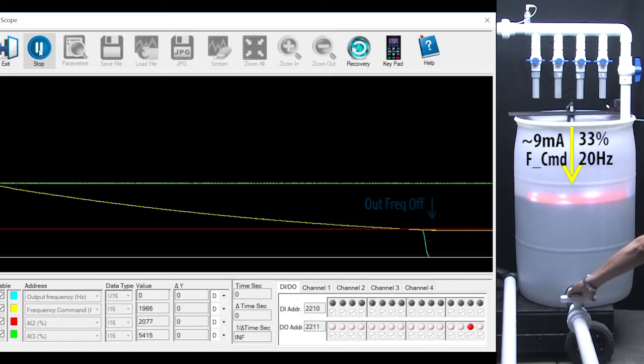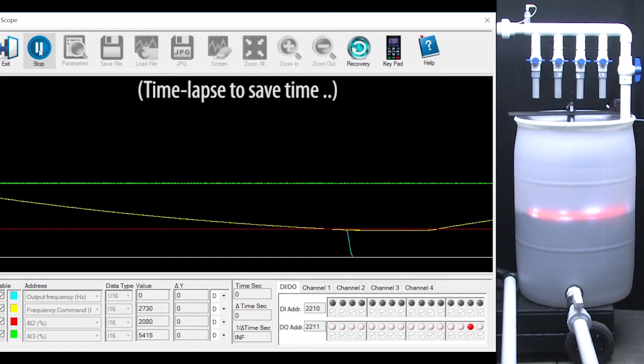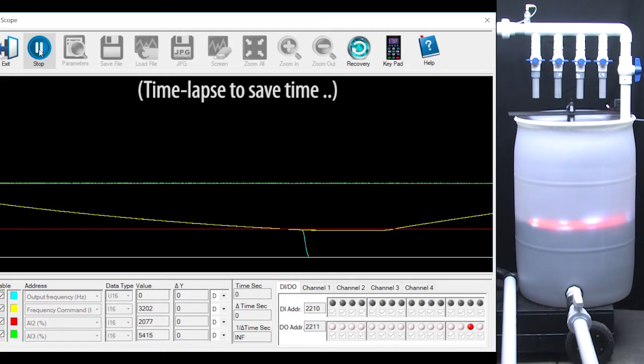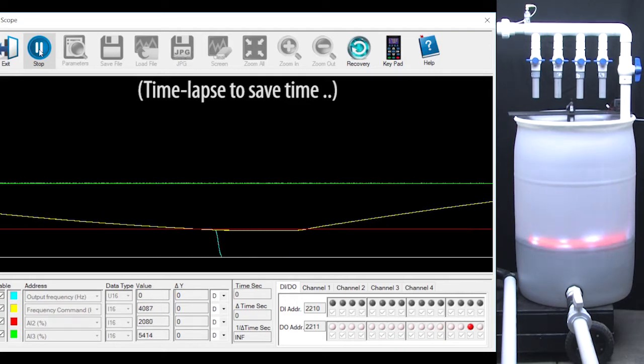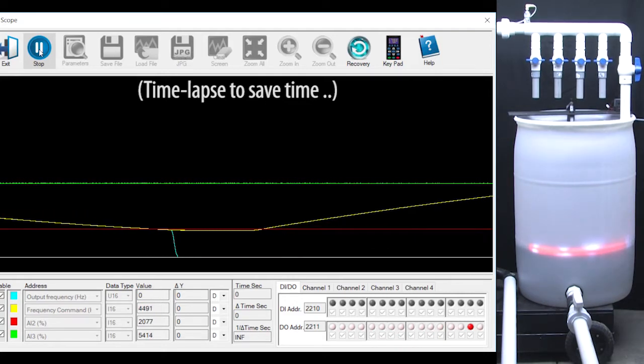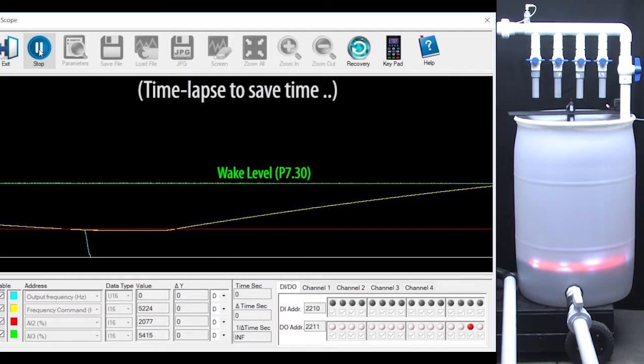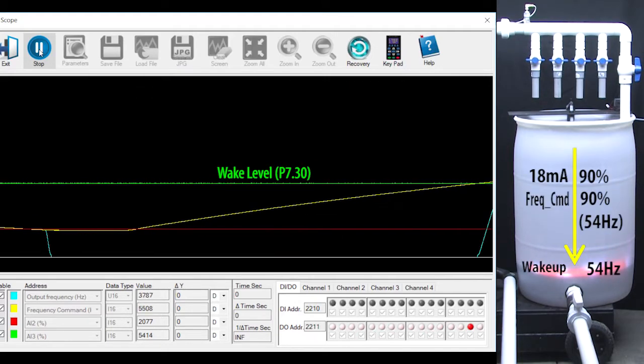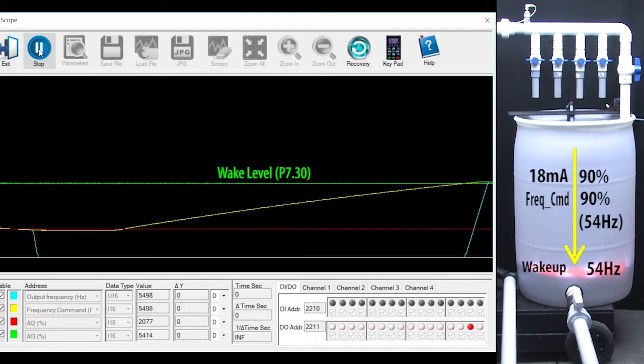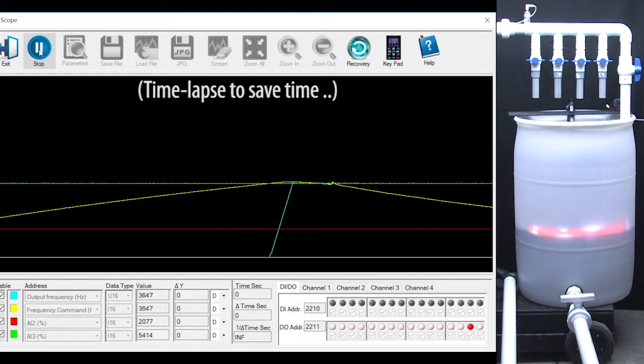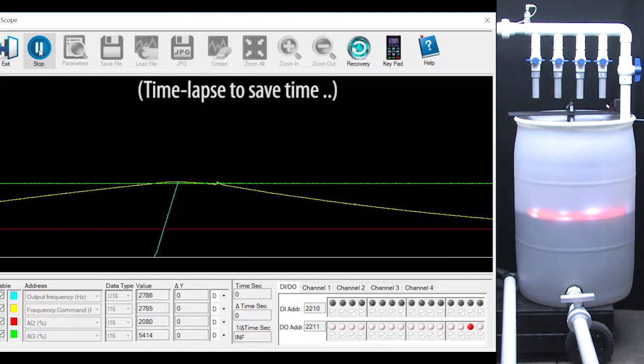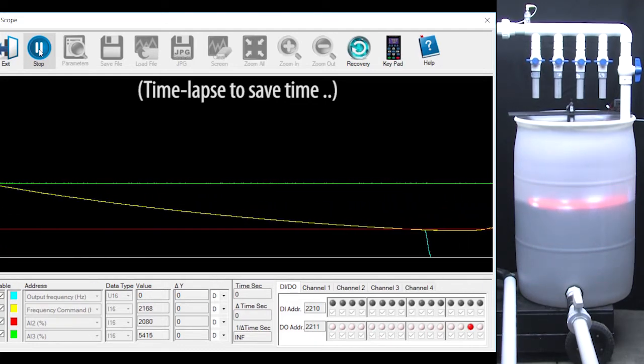I am going to open this valve to simulate demand on the tank. As the water level falls away from the sensor, the sensor signal gets larger and larger until it passes the wake up level we set in parameter 730 where the motor turns back on again and repeats the cycle endlessly. That's sleep mode in a nutshell.